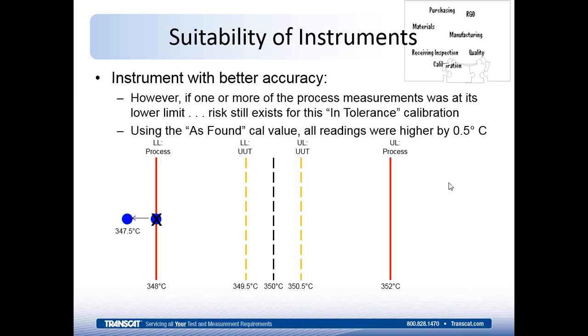So if one or more of those process measurements in a 4-to-1 ratio was at the lower limit in this example, and we found the instrument to be at its upper tolerance when it was calibrated the next day, going back to those process measurements, those that were at the lower limit or within that region for that tolerance of the instrument would be considered to be bad measurements.